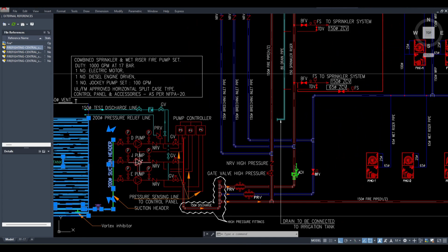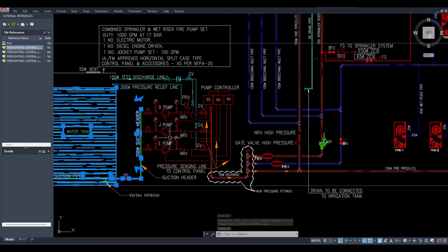Okay, then suppose because of the fire your wire is burnt out, or these both pumps are electrical pumps, so both are not able to work. In that case you will have another pump of the same capacity as the electrical pump, the diesel pump. Okay, so this will start, the diesel engine is there, and it will start working on diesel, so it does not require any electricity. So even if the wires are burnt and this control system and all these things are not working, the diesel pump can work and deliver the water. So it's like two times protection. Okay, so that's why all these lines are there.